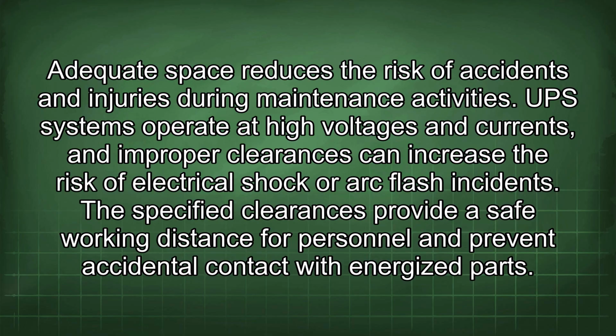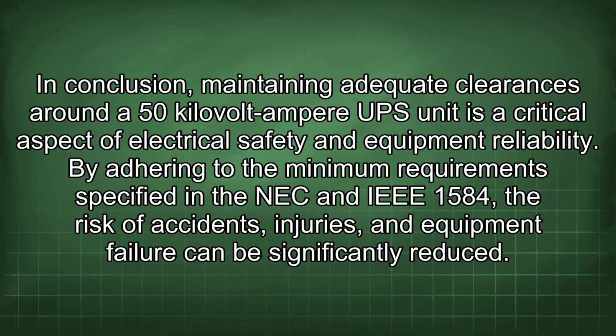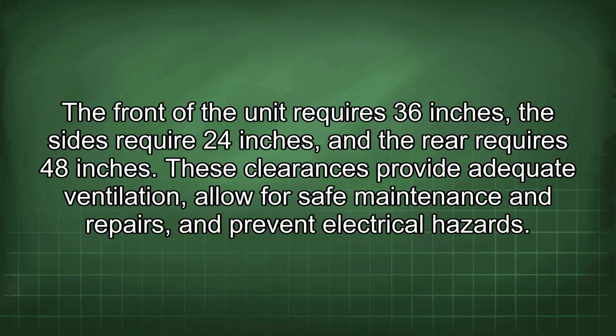UPS systems operate at high voltages and currents, and improper clearances can increase the risk of electrical shock or arc flash incidents. The specified clearances provide a safe working distance for personnel and prevent accidental contact with energized parts. In conclusion, maintaining adequate clearances around a 50 kilovolt-ampere UPS unit is a critical aspect of electrical safety and equipment reliability. By adhering to the minimum requirements specified in the NEC and IEEE 1584, the risk of accidents, injuries, and equipment failure can be significantly reduced. The front of the unit requires 36 inches, the sides require 24 inches, and the rear requires 48 inches. These clearances provide adequate ventilation, allow for safe maintenance and repairs, and prevent electrical hazards.